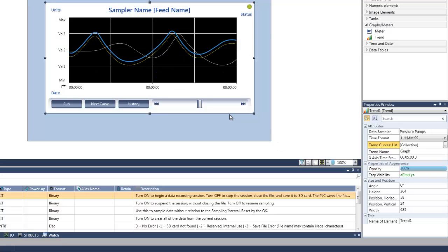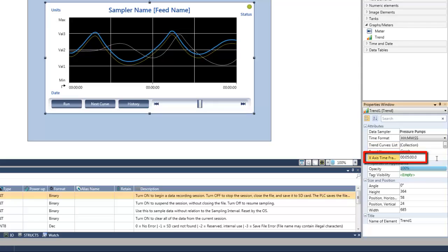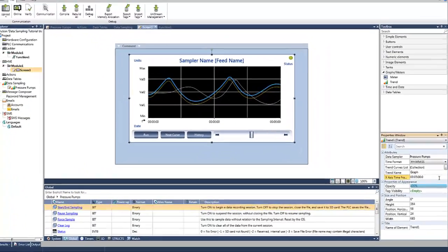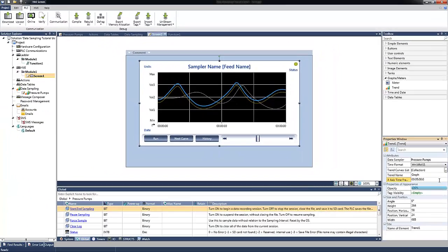Let's close now the curve configuration. And another attribute we can change at the trend properties is the x-axis time frame, which by default is five minutes. And for now, we will leave it as default. In order to stop and start the data sampling, we will need to set the start end sampling tag. Let's take a button and place it on the HMI.